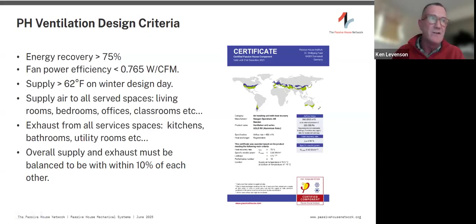Boom, boom, boom. This last bullet point is an important new item, and that is that supply and exhaust air coming into the building to the unit and out of the unit to the exterior, it needs to be within 10% of each other. The units need to be balanced, and we'll talk about that a bit in the commissioning. We don't want to pressurize or depressurize the building. We want the air to get to where it needs to be, and we want it to be done efficiently.